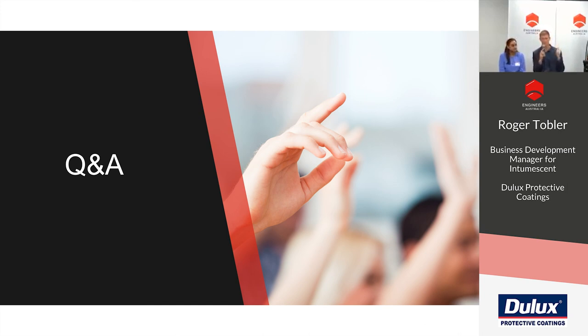So the loading tables and the data that Suki prepared would be only global, the standard is the same for everyone. Every intumescent company would test like that. Okay. Yeah, that's right. So the outcome tables and the regression equation are all prepared using DFT only, which is dry film thickness. And you will normally give them a range of DFTs that you've tested your top coat on?